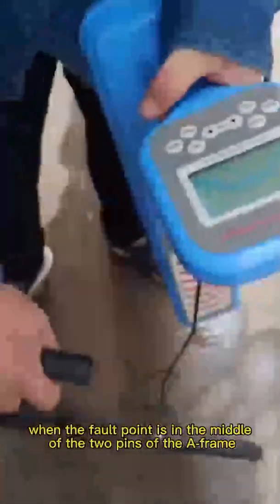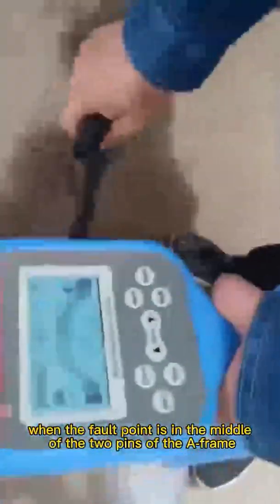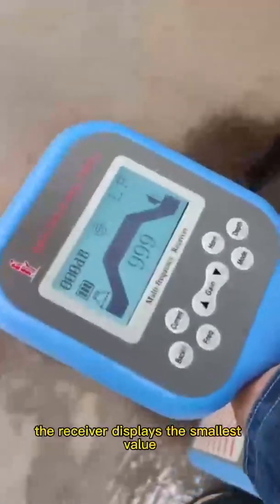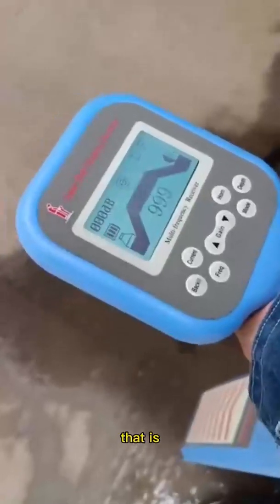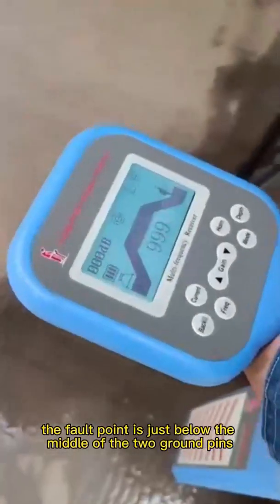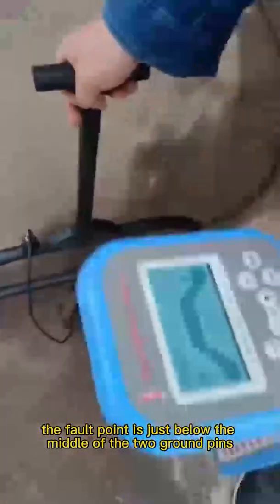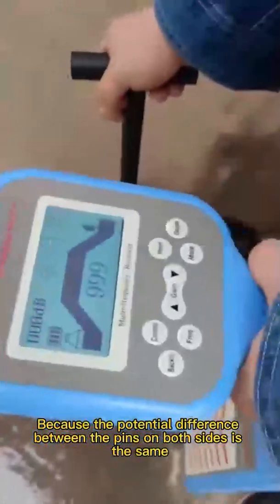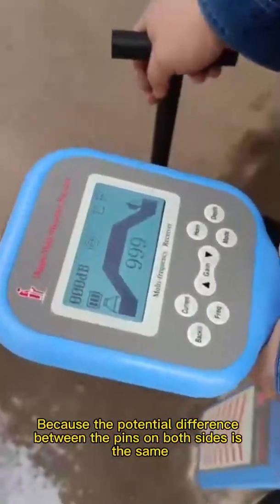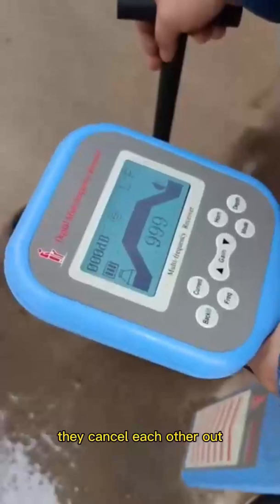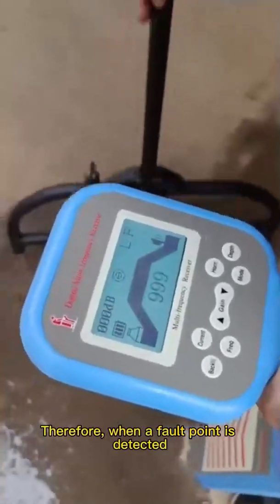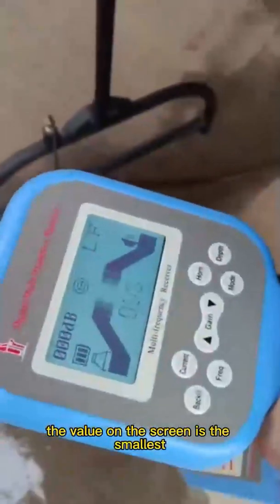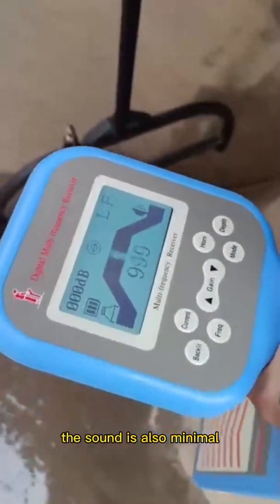When the fault point is in the middle of the two pins of the A-frame, the receiver displays the smallest value, that is, the fault point is just below the middle of the two ground pins. Because the potential difference between the pins on both sides is the same, they cancel each other out. Therefore, when a fault point is detected, the value on the screen is the smallest. The sound is also minimal.